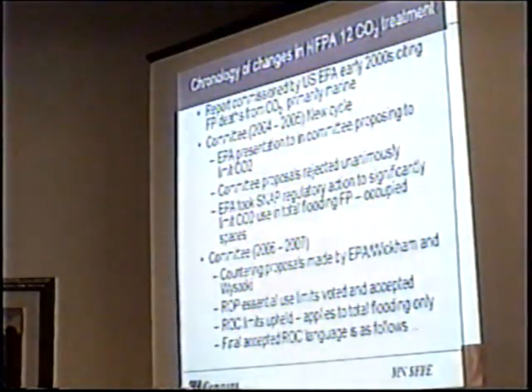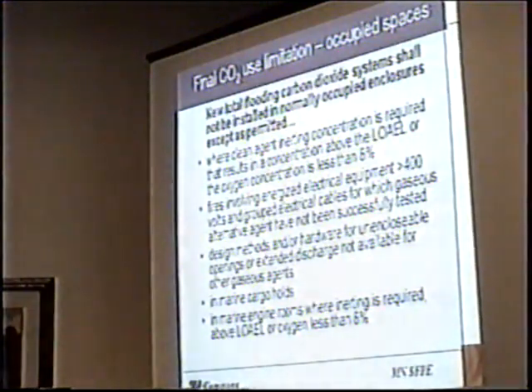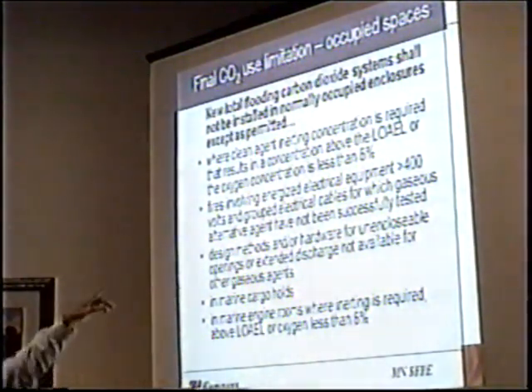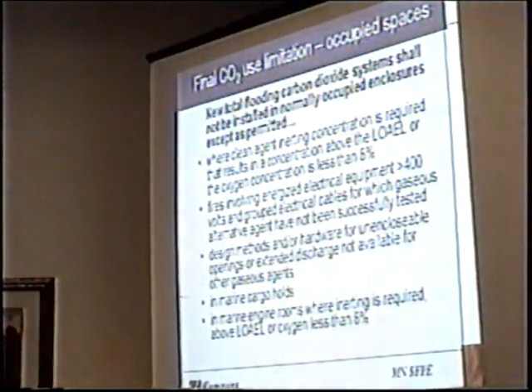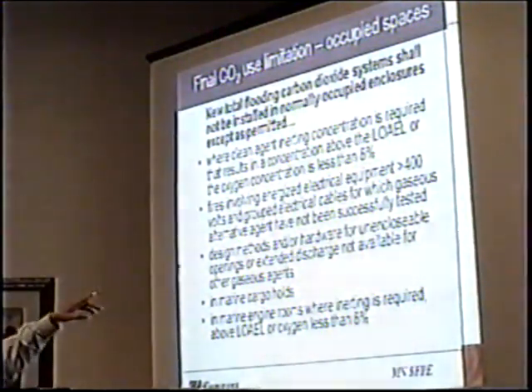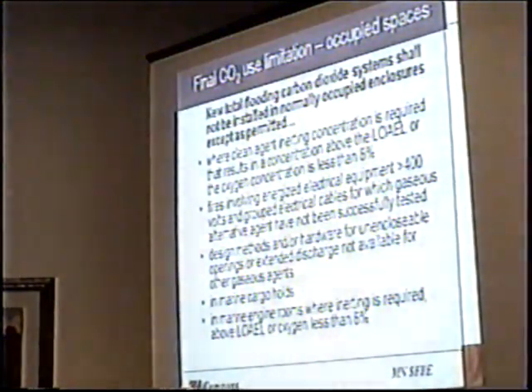Final accepted ROC language is as follows. As you look at it here, new total flooding carbon dioxide systems shall not be installed in normally occupied enclosures except as permitted: where clean agent inerting concentrations, much higher concentrations, are required that result in a concentration above the LOAEL, the lowest observed adverse effect level. That's a level that's higher, where an agent shows an adverse effect. Or where the oxygen concentration is less than 8% in the case of inert gases. Fires involving energized electrical equipment over 400 volts. Again, where did that come from? Don't know. It was pulled out of a hat. And grouped electrical cables for which gaseous alternative agents have not been successfully tested.